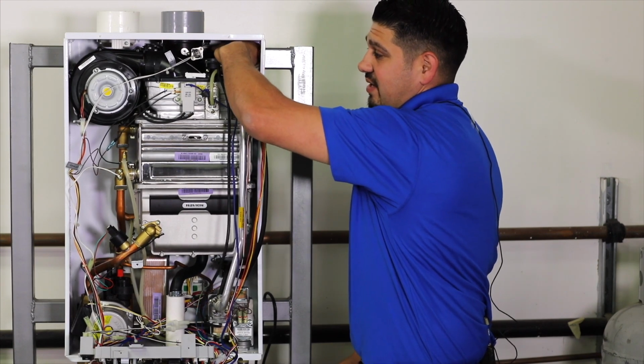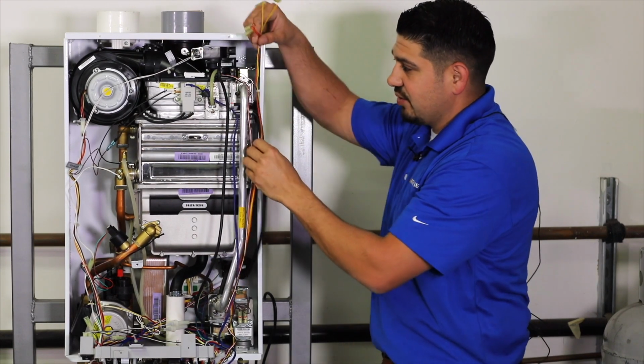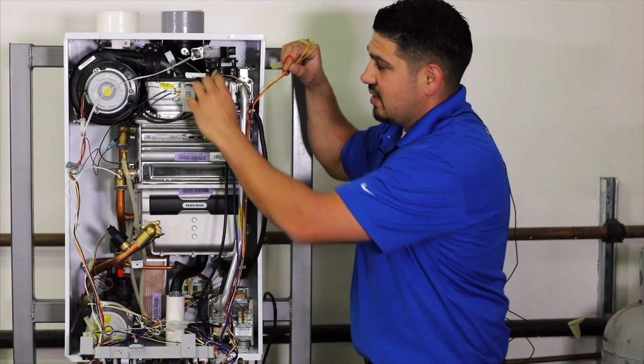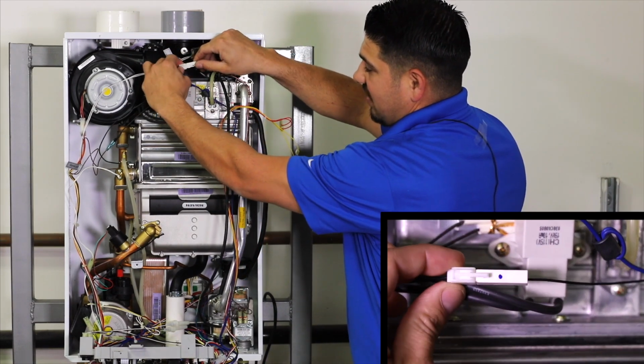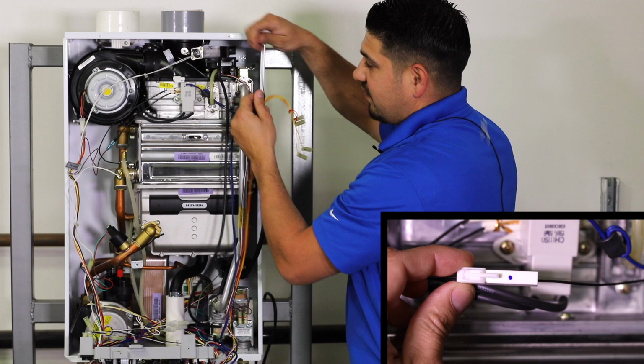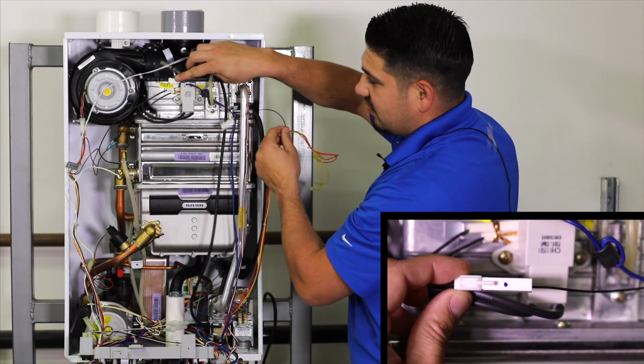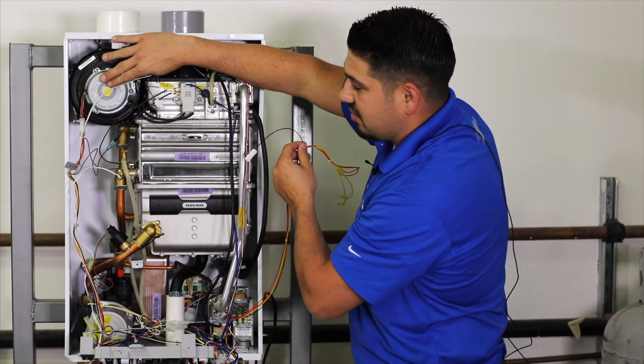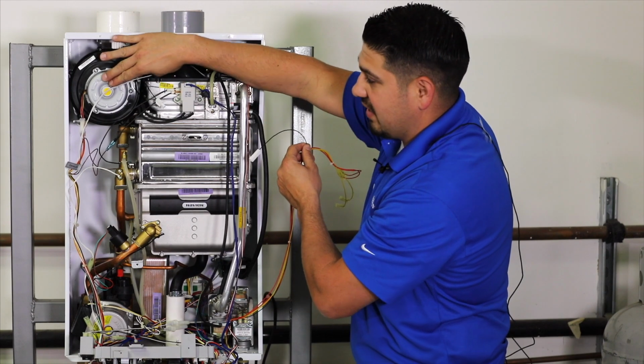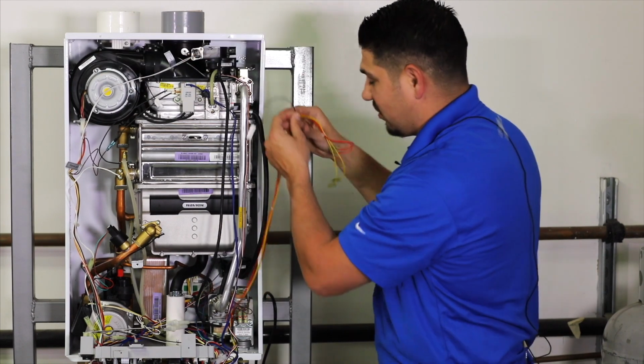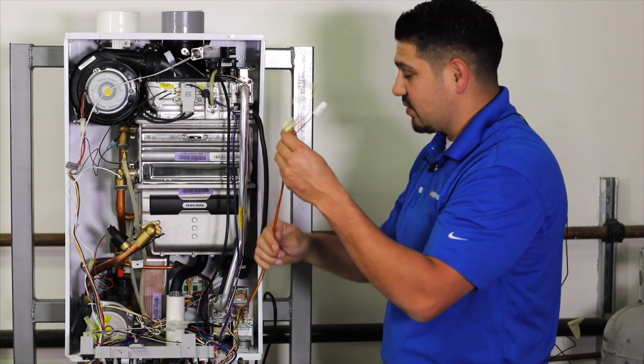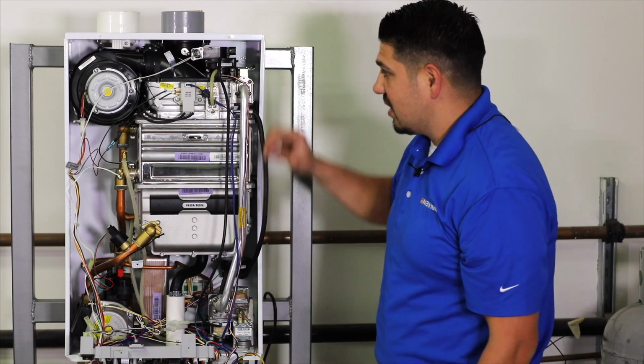You're going to have to get your hand back in there. So your solenoid wires are now disconnected. We're going to disconnect this black wire, which is your flame rod. So this black wire is going to go down, chasing underneath in between your burner and your fan. That's where your flame rod is connected or located. So now this section of the wiring harness is done.